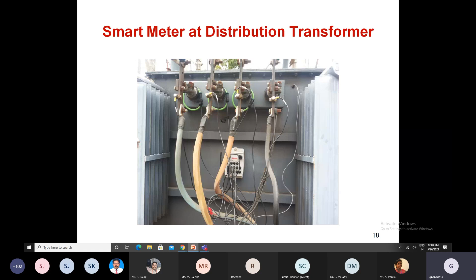That is the advantage of connecting the smart meter at the output — the utilization of the transformer is high. Not only that, we can also observe the loading point of R, Y, B from here. Look at this distribution transformer data: it's time-stamped with the year, month, and time it was taken, along with the current and voltages, and the usage rate of the windings of the transformer. If there is an over-voltage problem, it will intimate the control center.